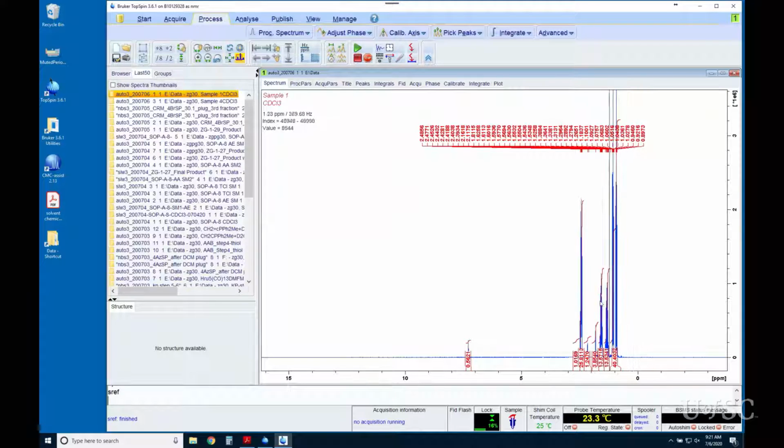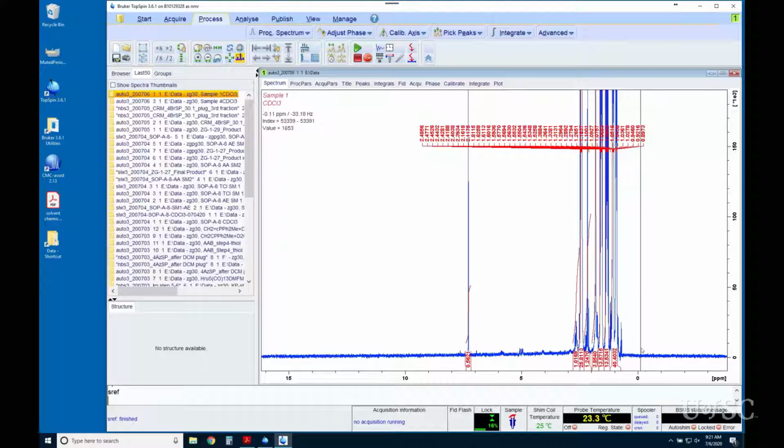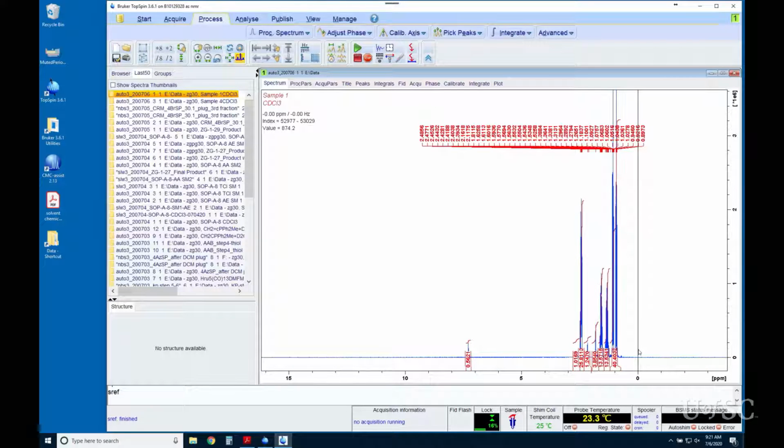However, it is difficult to get consistent chemical shift results across many samples without further referencing. One problem with SREF is that it sometimes finds a peak near where TMS would be and sets it to 0 ppm. This is common for samples contaminated with stopcock grease or silicone-based vacuum pump oil. This could lead to chemical shift errors of over 1/10th of a ppm.